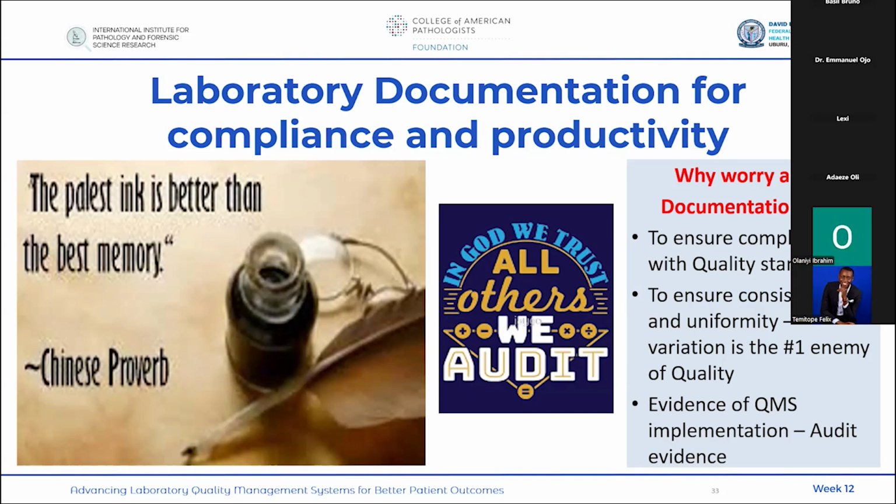Dr. Emmanuel, yes, we did this. We did our IQC, we reviewed it. I'll be nodding my head and I'll be waiting for you to provide the evidence of that implementation. And if you are unable to provide that, I will simply note that at the time of audit, IQC was not performed and there is no record to show that they are being reviewed. So it's not about swearing the name of God that, oh, we did it. Once it is not documented, there is no way I can believe you.